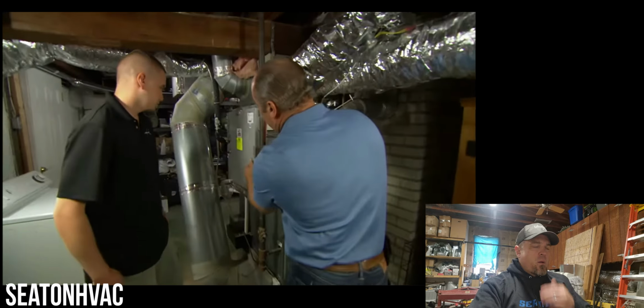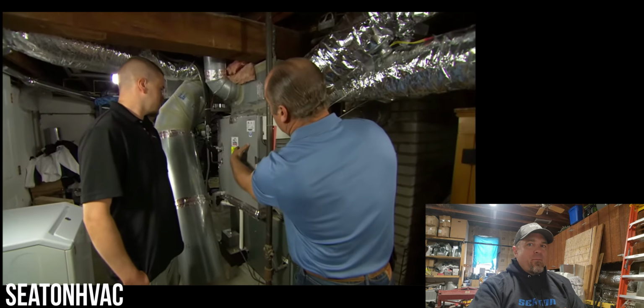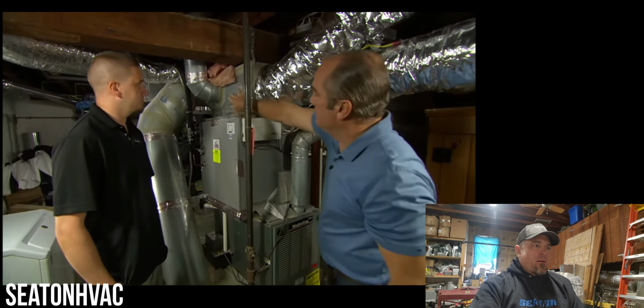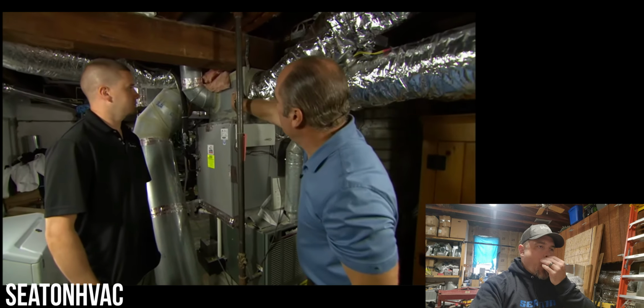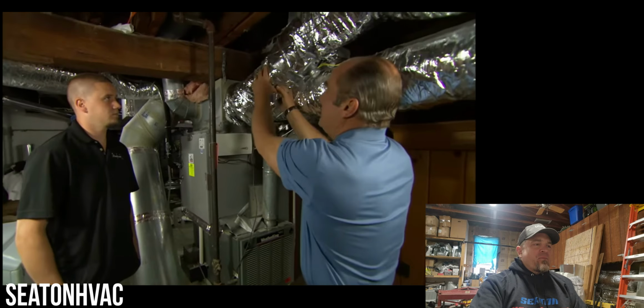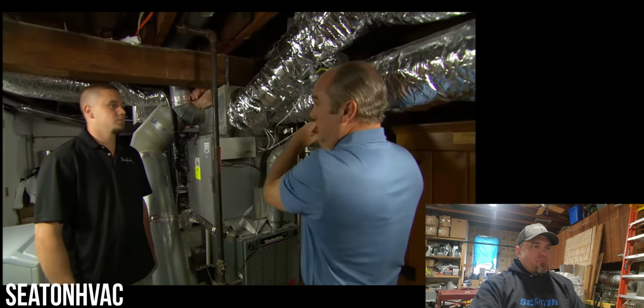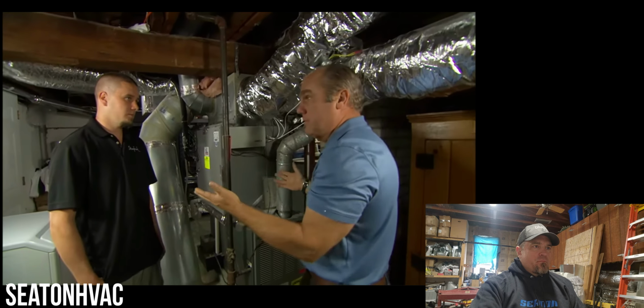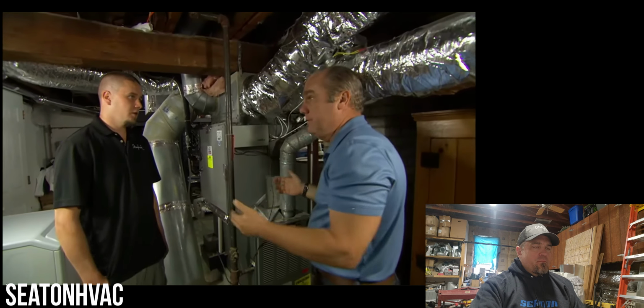Across this box right here for cooling, there's a cooling coil here. The air goes up into this box at the top called a plenum, and right here are the supply ducts that go out to all the individual registers. That's how it's supposed to work. What's going on with yours? Well, during the summertime, I turn it on, and the system runs for about an hour, and then it stops working. So I come down here to check it out, and I notice that this is all frozen up.